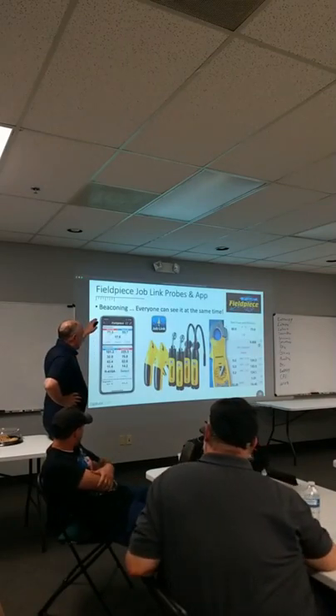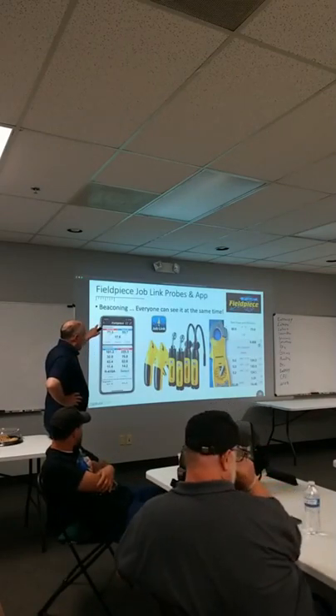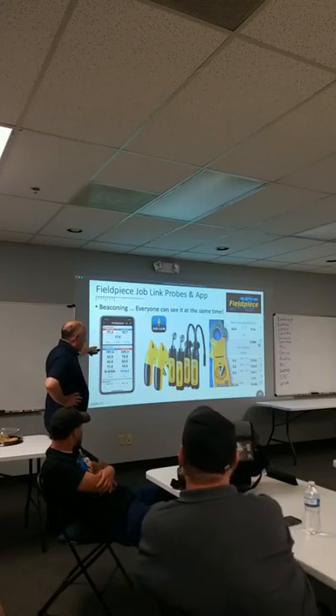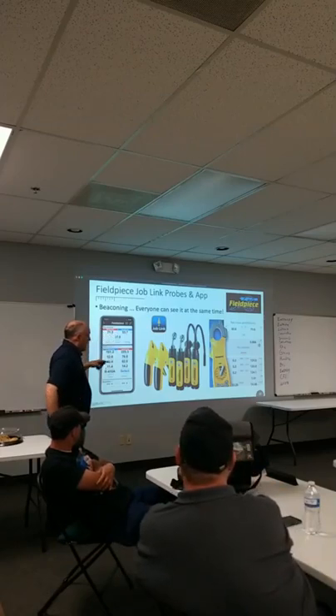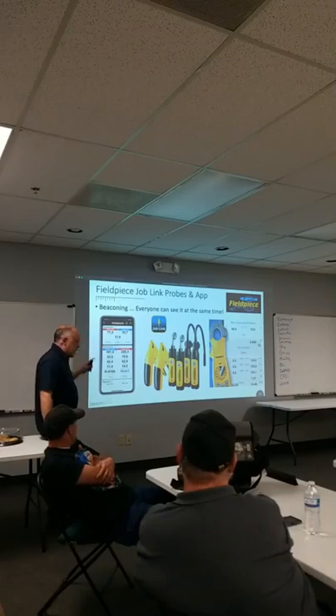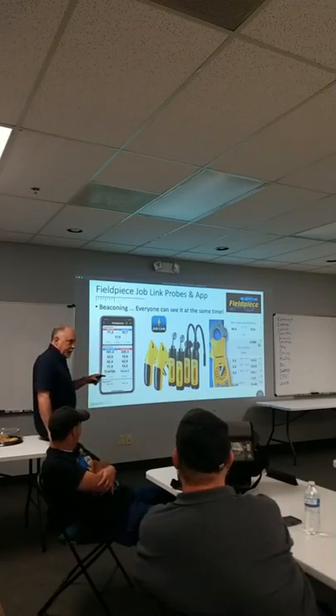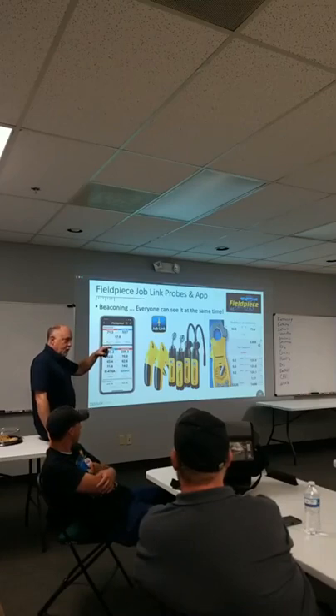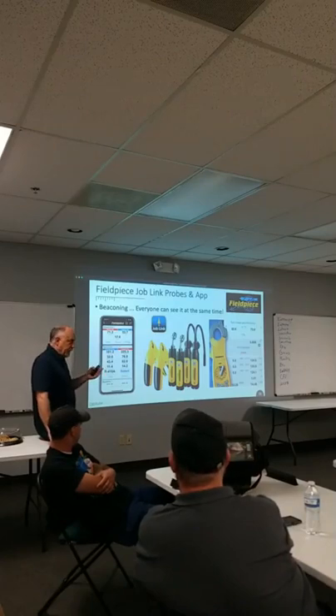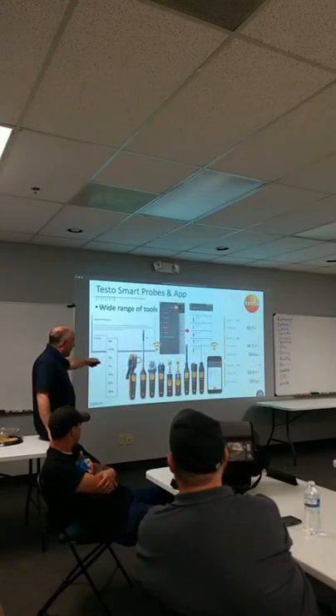Fieldpiece, we use a lot of in MeasureQuick, and the reason we like them is because they beacon the signal. So we're using Fieldpiece probes in an educational setting, like if you guys were all in here, you have one set of probes connected to one piece of equipment, and everybody in the room can connect to those probes at the same time. That's a huge advantage when you're trying to do training, being able to let everybody connect and see what's going on.